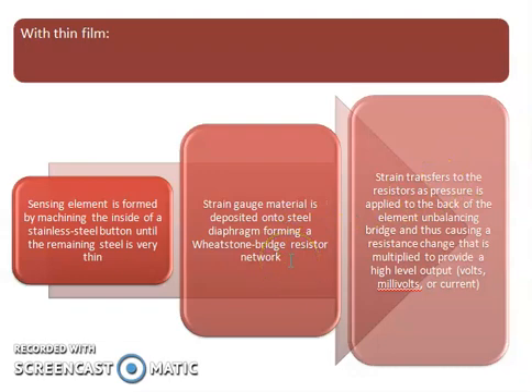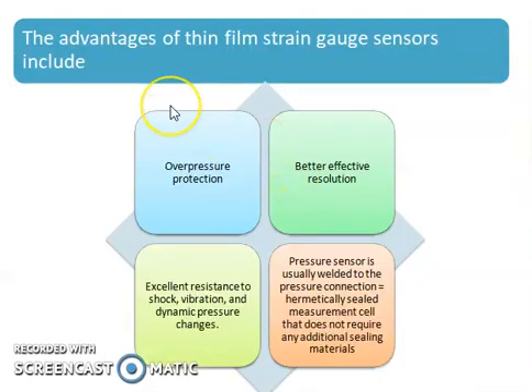That is, whenever strain occurs, the balance of the Wheatstone bridge is changed, and due to that unbalancing, we get a voltage at the output of the Wheatstone bridge which is proportional to the pressure that we applied on our strain gauge. That is, strain transfers to the resistor as pressure is applied on the back of the element, unbalancing the bridge and thus causing a resistance change that is multiplied to provide a high level output, that is volts, millivolts or current.